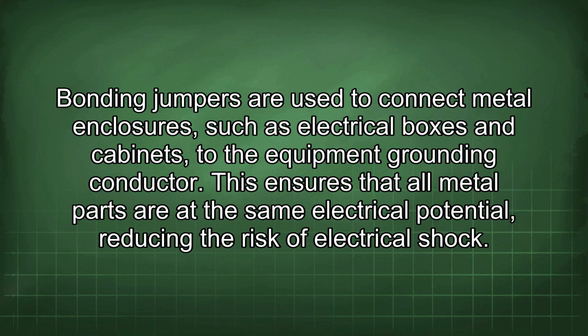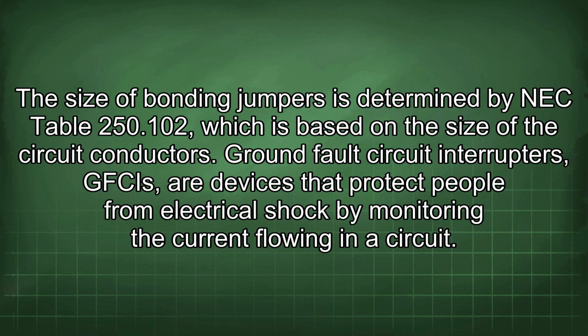This ensures that all metal parts are at the same electrical potential, reducing the risk of electrical shock. The size of bonding jumpers is determined by NEC Table 250.102, which is based on the size of the circuit conductors.